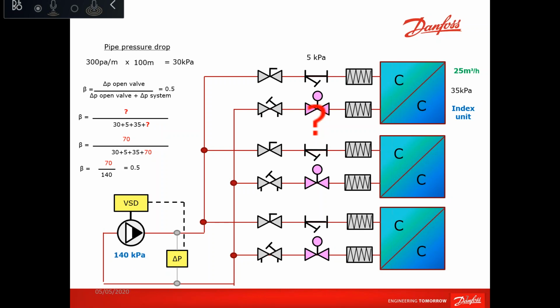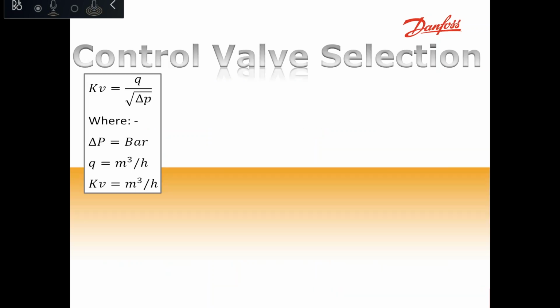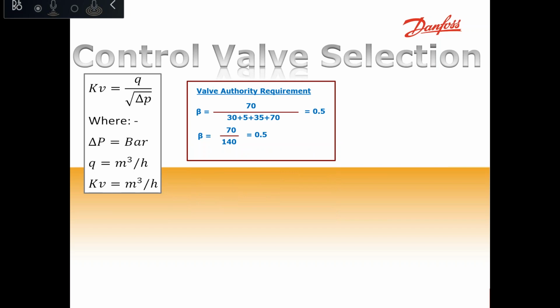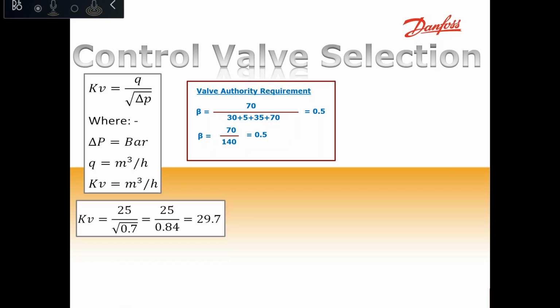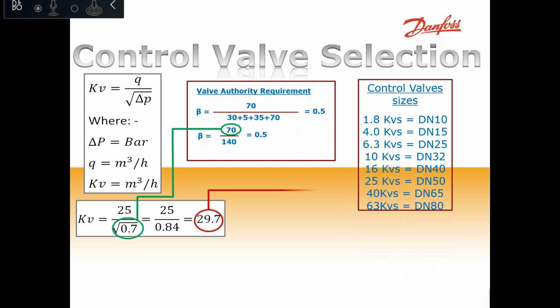Now, if we go and select the valve in the manufacturer data sheet, you cannot find your calculated kV, but you will only find the predefined or manufactured standard kVs. So in our case, we have a flow of 25 cubic meter per hour, and we have 70 kPa, which is the pressure drop we need to have an authority of 0.5. If we go and calculate the kV, we will have 29.7. And 29.7 is not a custom-made two-way valve, but the closest valve to it is 40 kV, which is the DN65.